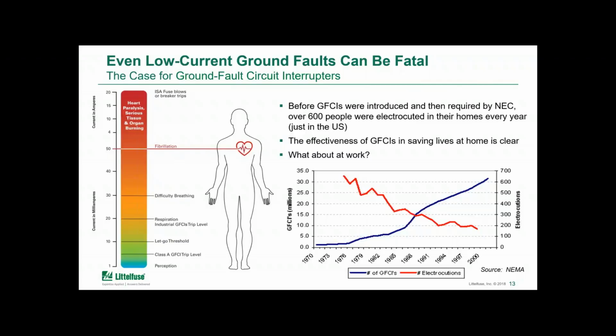For comparison, it takes about 50 milliamps for an adult heart to go into fibrillation. Now you can see the other lines listed on there as well, indicating that respiration is affected and difficulty breathing can occur. And just to clarify there, when I mentioned the let-go threshold at 10 milliamps, a Class A GFCI is not going to limit the fault current. The Class A GFCI will begin picking up at a 6 milliamp level. So I just wanted to make that clear.